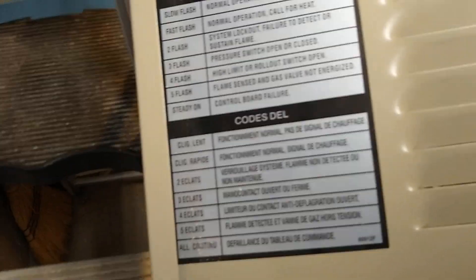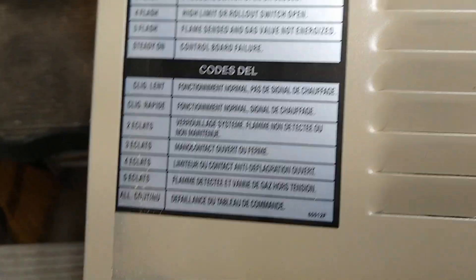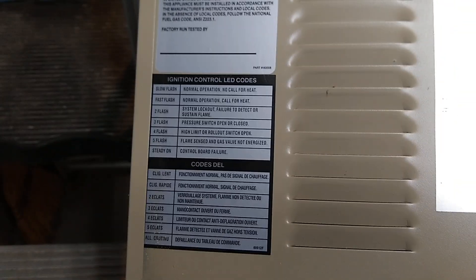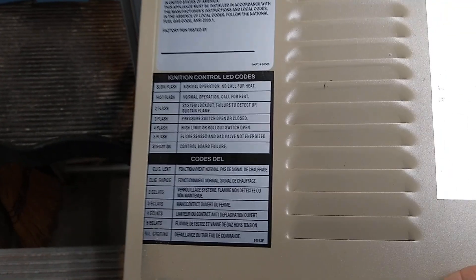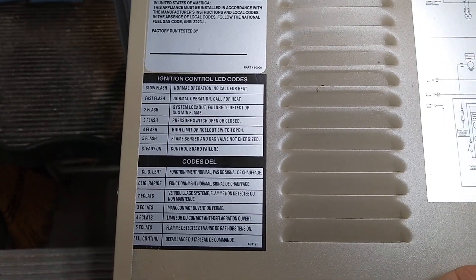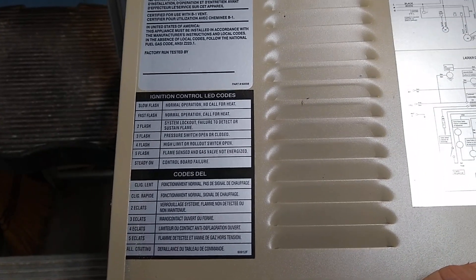But if you look at this LED blink code, you're getting three slow green, or actually it's just a single LED. And if you look at the panel, this is, you have three flash pressure switch open or closed.